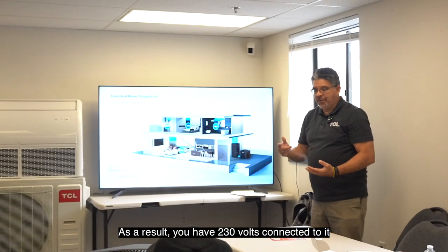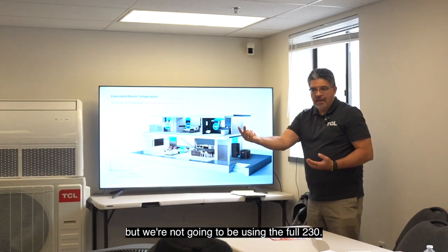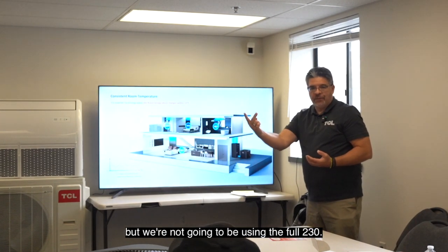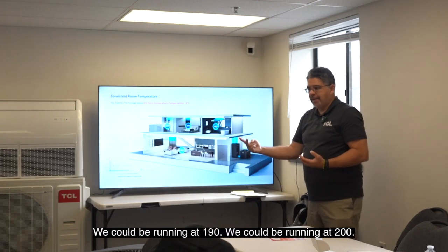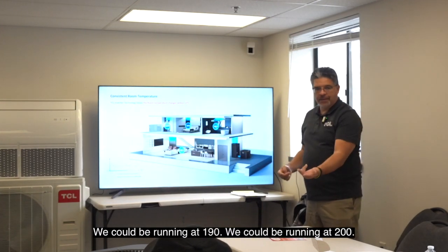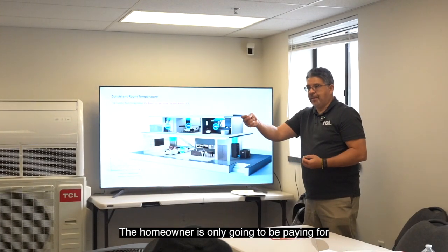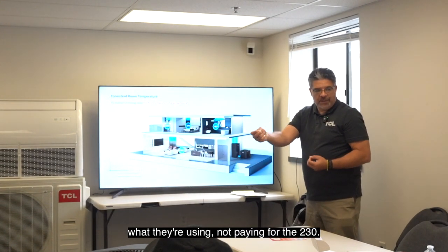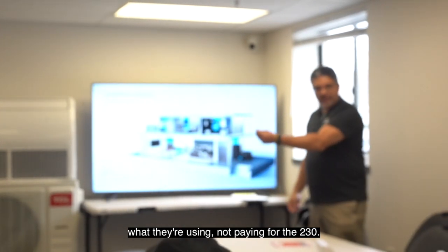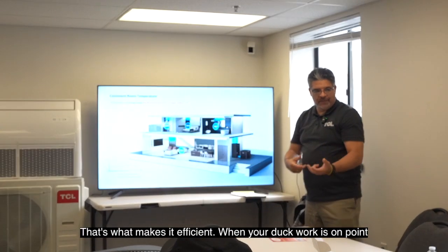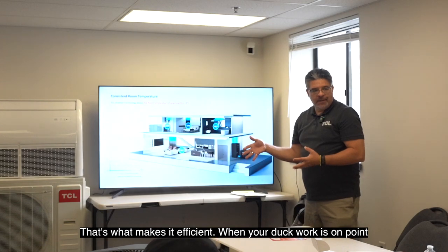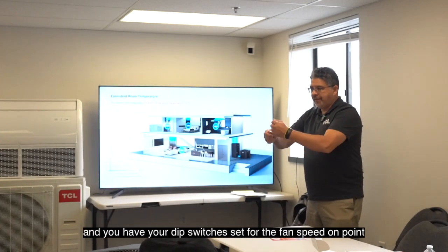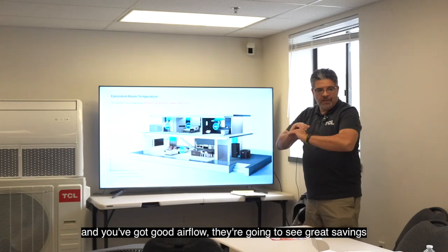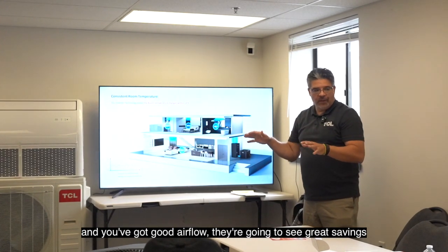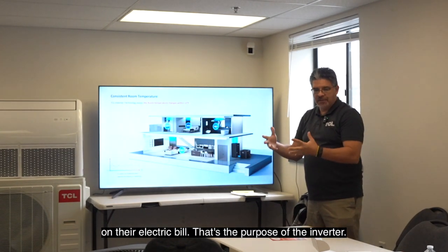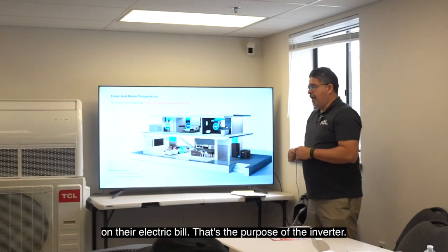And as a result, you have 230 volts connected to it, but we're not going to be using the full 230. We could be running at 190. We could be running at 200. And so the homeowner is only going to be paying for what they're using, not paying for the 230. That's what makes it efficient. And when your ductwork is on point, and you have your dip switches set for the fan speed on point, and you've got good airflow, they're going to see great savings on their electric bill. That's the purpose of the inverter, okay?